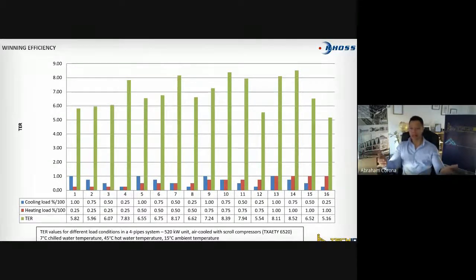What happens if you have 600 kilowatt of cooling, 400 kilowatt of heating? In that moment, running only a 4-pipe unit could be more efficient than doing independent systems, boiler and chiller, but it could be not running at the best efficiency point. So for what we call an EXP system, we have now developed what we call a smart sequencer. The sequencer is more a controller that will be connected to any unit and would allow you to connect not only an EXP unit, but probably also a standard chiller or standard heat pump.